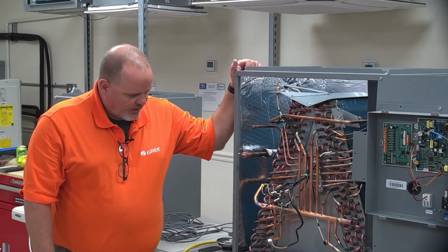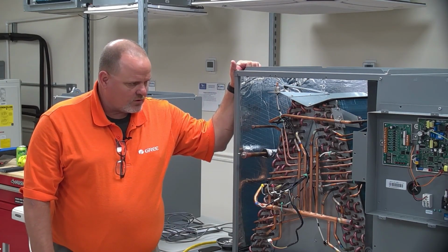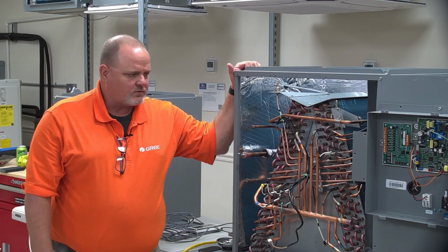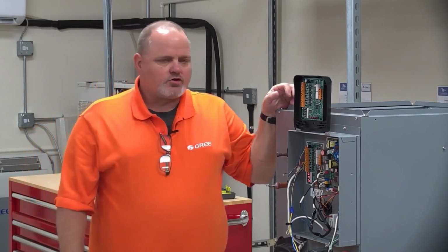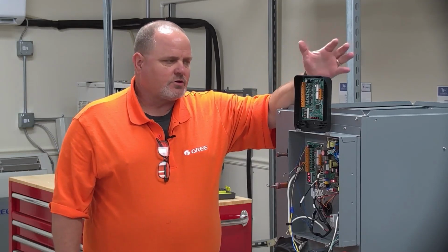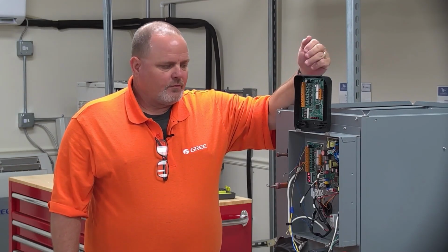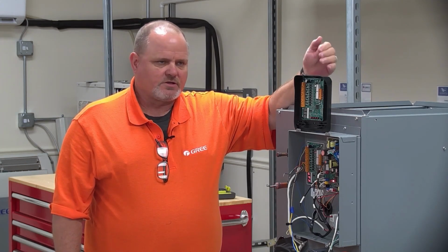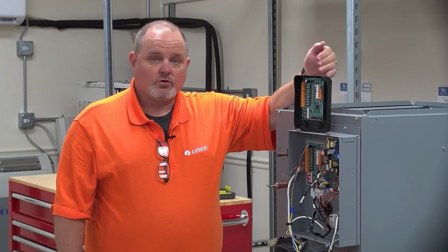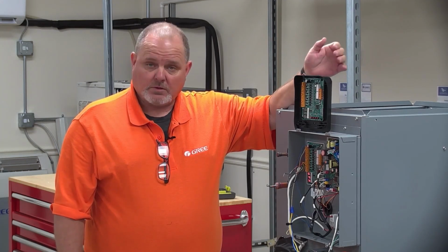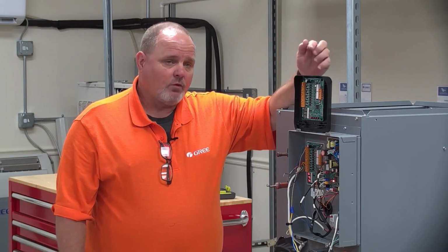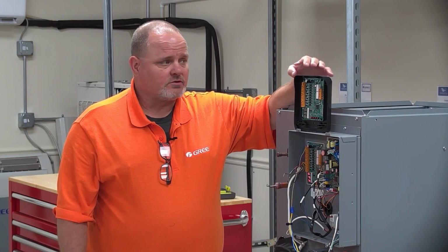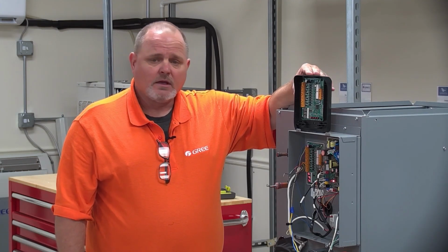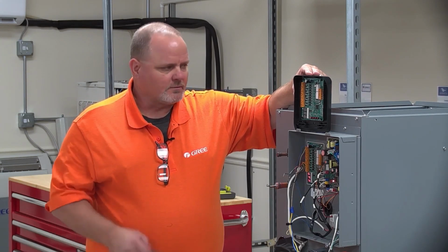So with that, let's move back to the controls and the functionality of it, and we'll go from there. All right, so getting into the wiring and the controls of this when you're doing a dual fuel application, the first thing I want to point out is that the board in here where you're going to be doing your thermostat connections is no different than the new 24-volt adapter, which we're going to be talking about shortly as well. But I have one of those new 24-volt adapters here, and it was just easier because I already got the other one hooked up that I can point out what you'd be doing here.